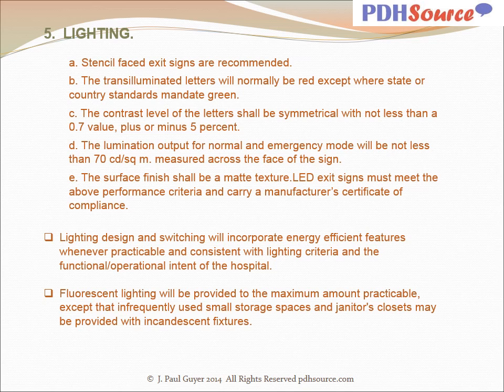LED exit signs must meet the above performance criteria and carry a manufacturer's certificate of compliance. Lighting design and switching will incorporate energy efficient features whenever practicable and consistent with lighting criteria and the functional operational intent of the hospital. Fluorescent lighting will be provided to the maximum amount practicable, except that infrequently used small storage spaces and janitor's closets may be provided with incandescent fixtures.